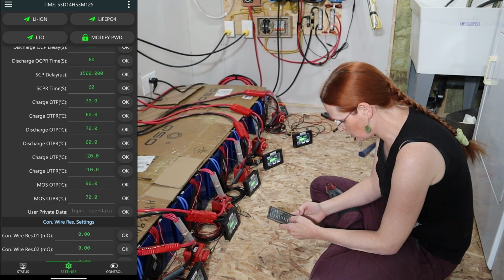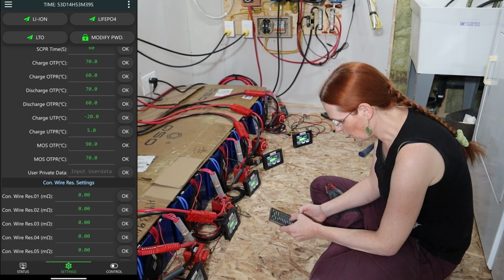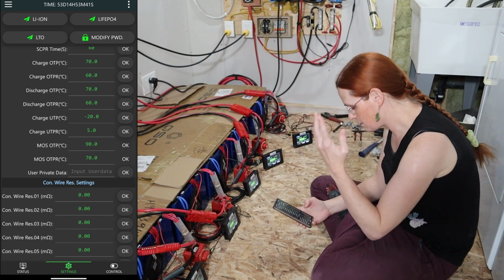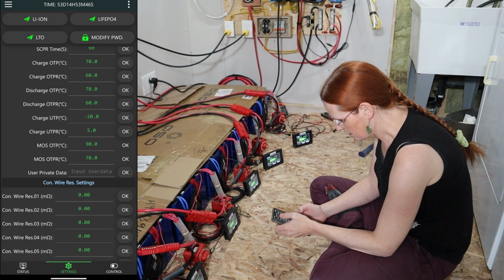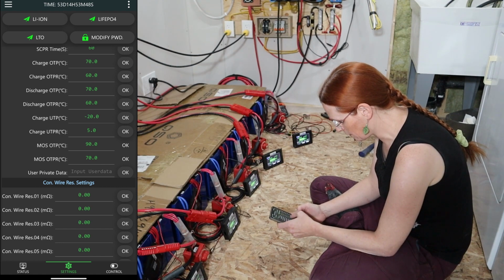Under temperature protection is -10. Charge - no, that should be, I think I'm going to set that to 5 degrees. Under discharge over temperature, discharge over temperature recovery, charge over temperature recovery, charge under temperature - no, these are, oh right, because this is not always for lithium iron phosphate. I'm glad I checked this.